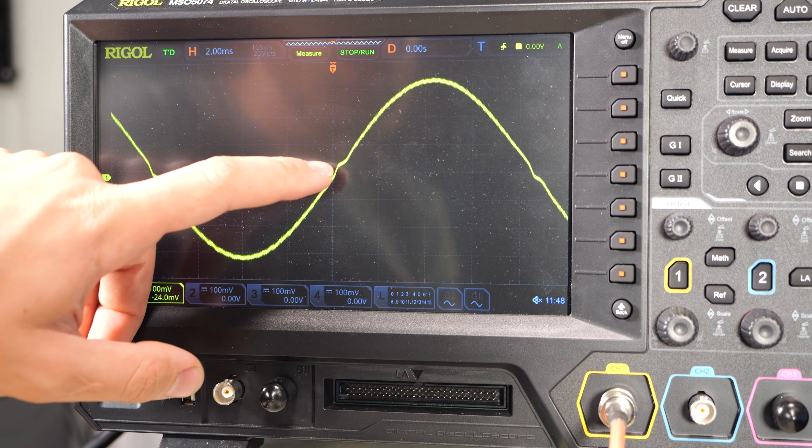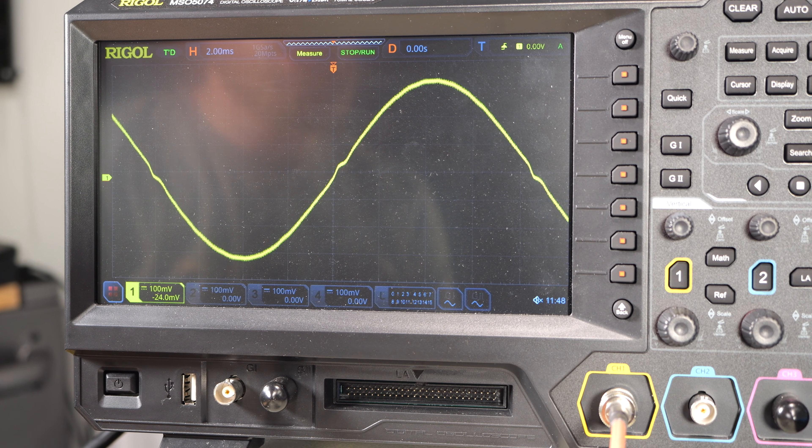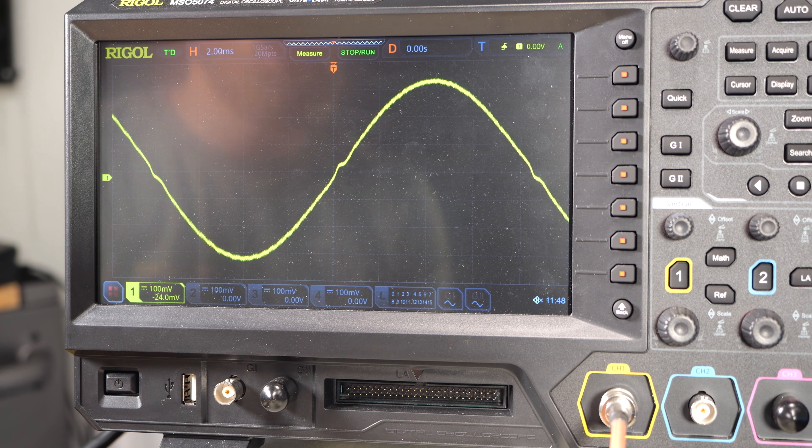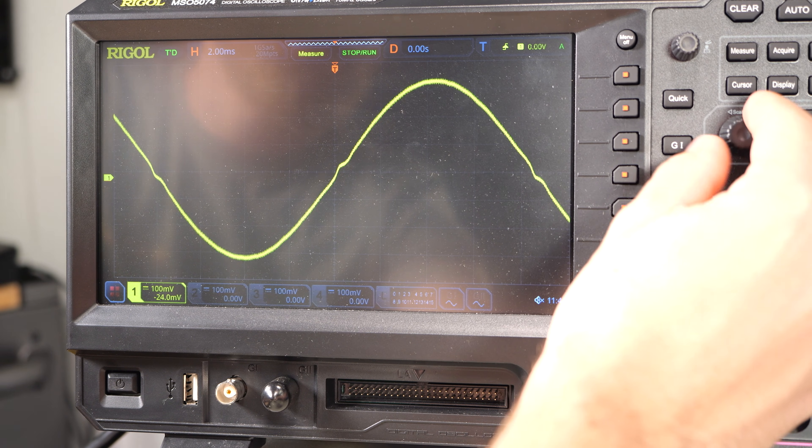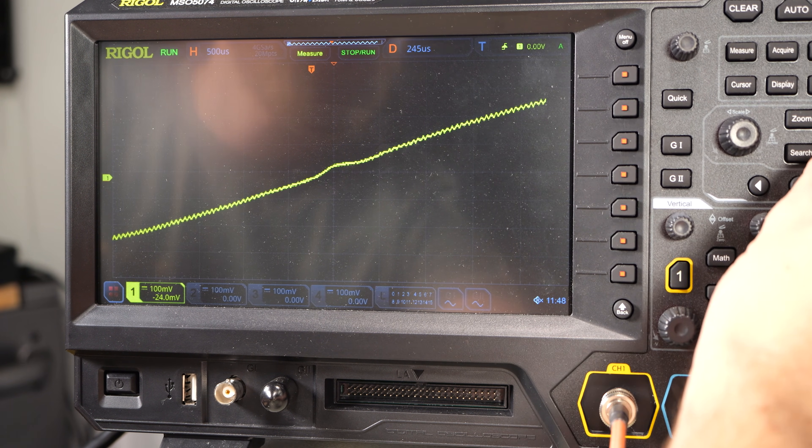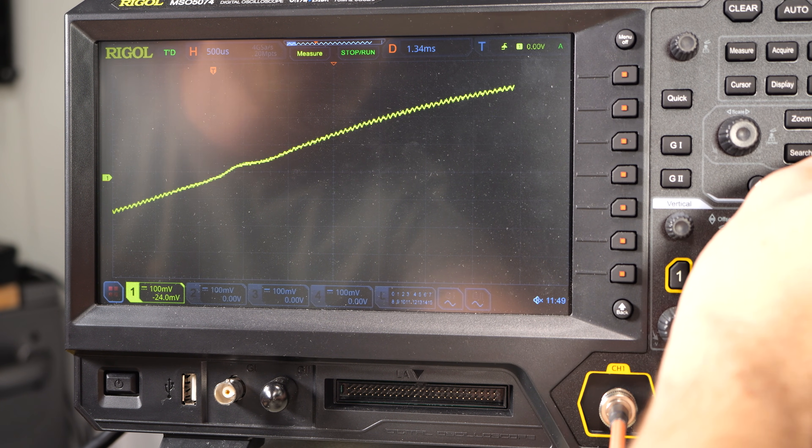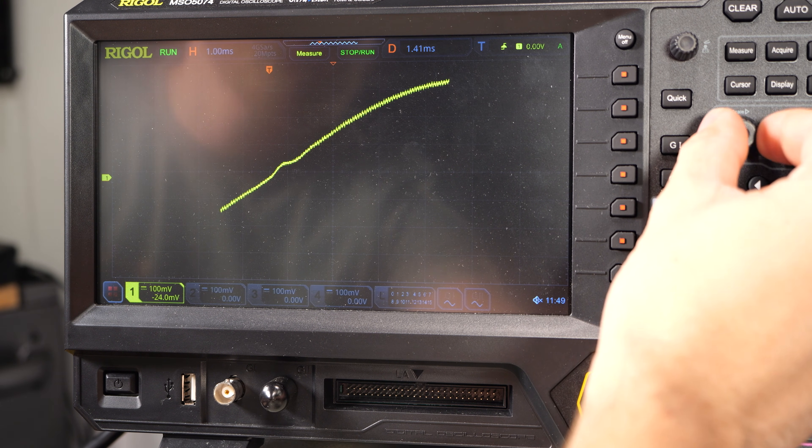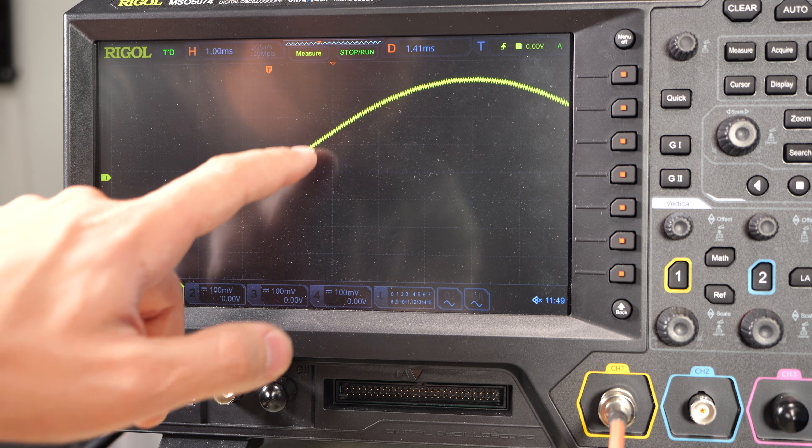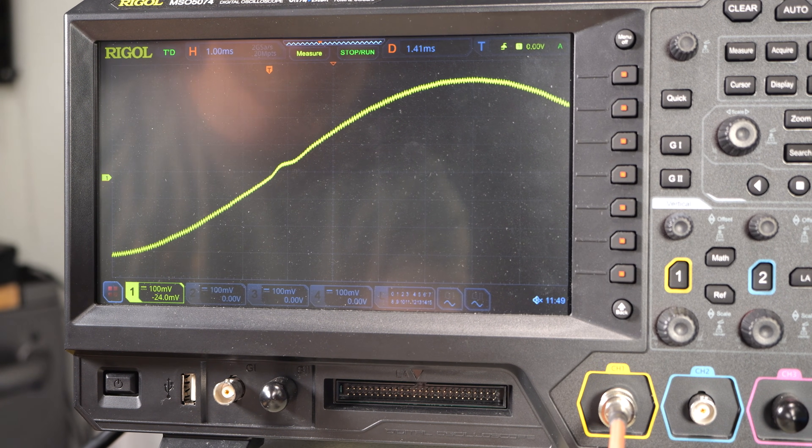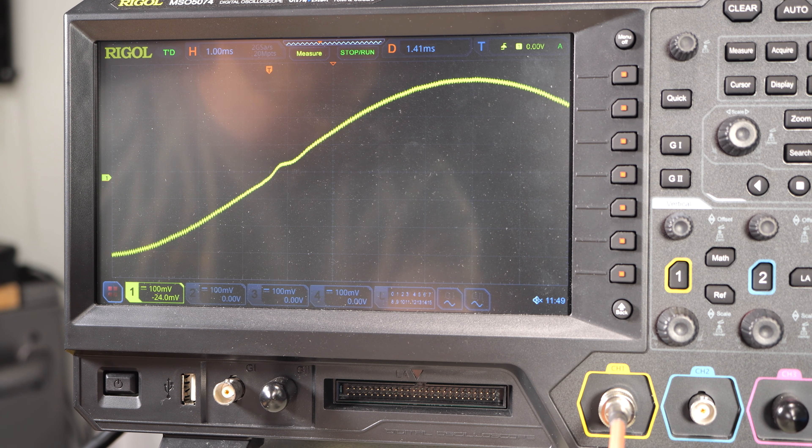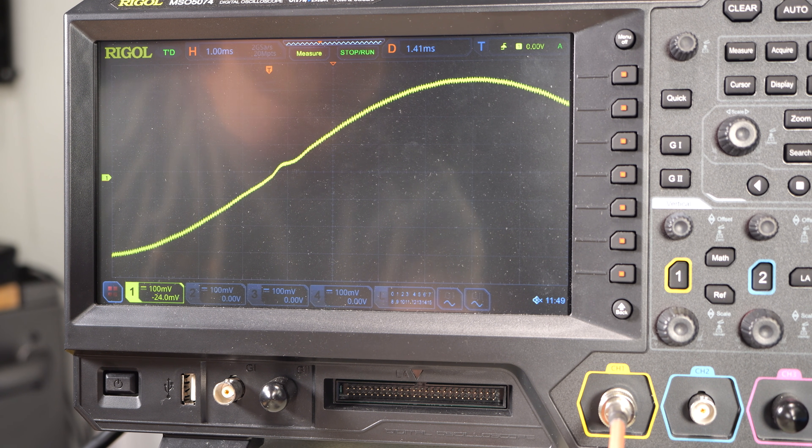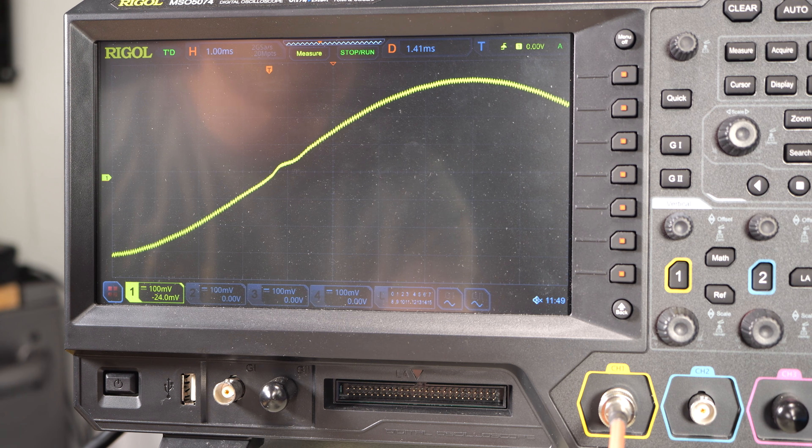So you can see there's a little bit of distortion right there at our zero crossing point. But other than that, it is pretty clean. There is a little bit of digital noise here. That's going to be our switching frequency of the H-bridge inside of the inverter. That's what causes that little bit of fuzz. But overall, this is a really good sine wave. And we'd expect nothing less with it having that big old transformer inside.